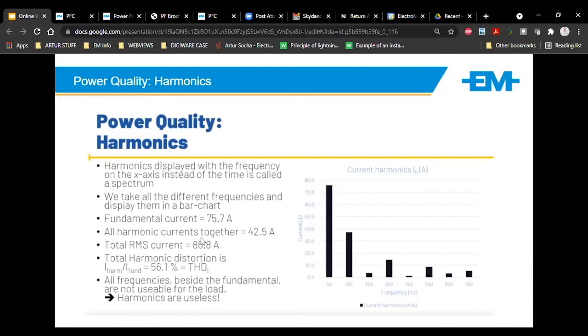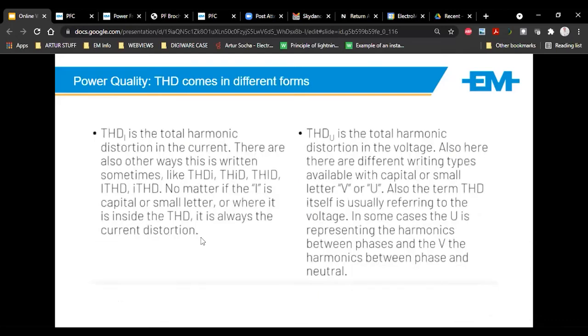So it's quite important to know, when I'm ramping up the drive or the load, if I have control, what does it do? How much harmonic distortion does it create? Is it a high percentage at a high load? That normally results in other issues. So THDI is the total harmonic distortion in the current. Different recorders might indicate this variable differently, but no matter what, THDI is current harmonic, and then you have THDU, which is voltage harmonic.